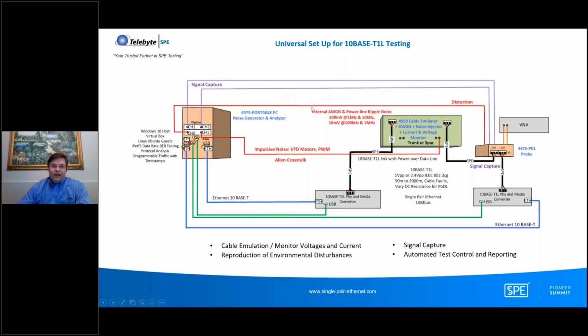And this shows you a cable wiring diagram where we have the digitizer going to the probe, and the probe is capturing the signals here. And then we have an AWG to generate the impulsive noise that we may measure from industrial environments. Then we have our cable emulator here where we're varying trunk or spur cable lengths, so we can test over different cable lengths, different DC resistance. We can introduce cable faults.